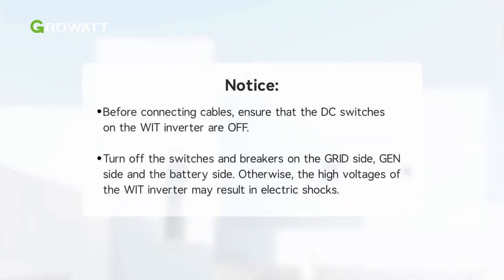Before connecting cables, ensure that the DC switches on the WIT inverter are off. Turn off the switches and breakers on the grid side, gen side, and the battery side. Otherwise, the high voltage of the WIT inverter may result in electric shocks.